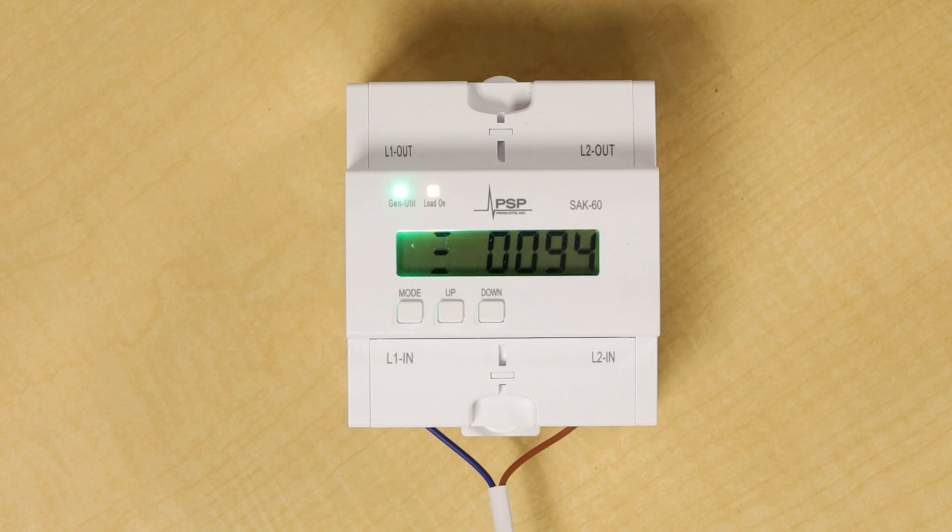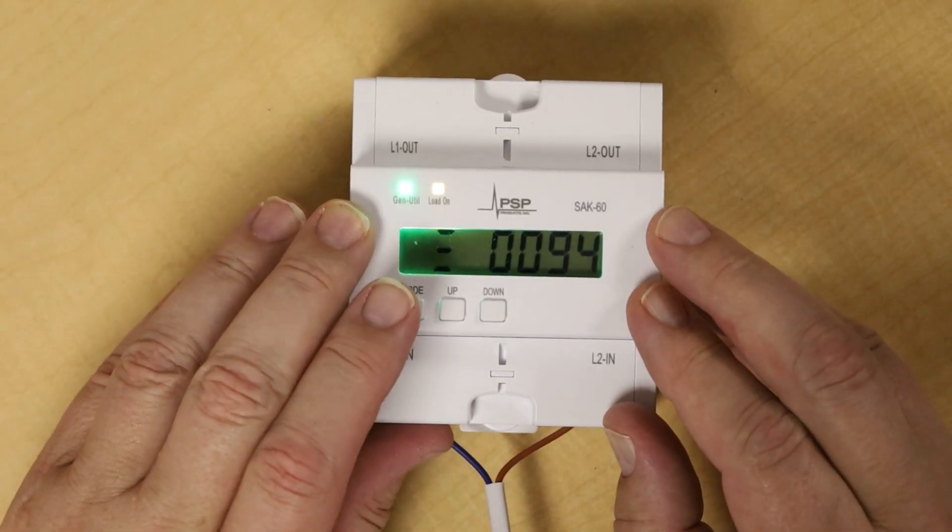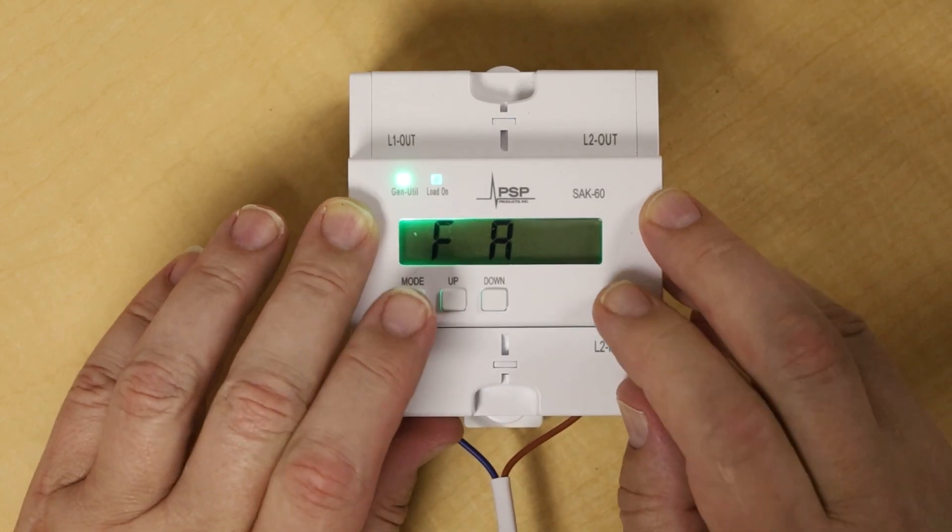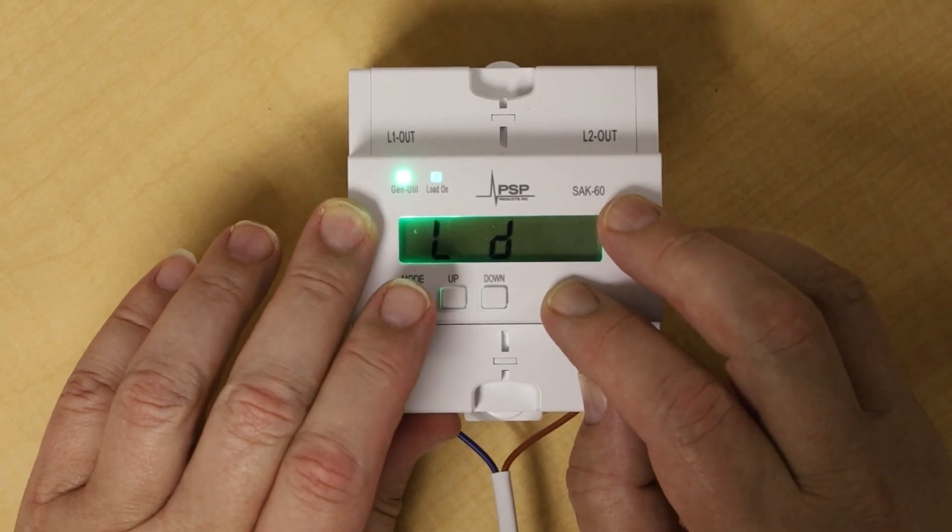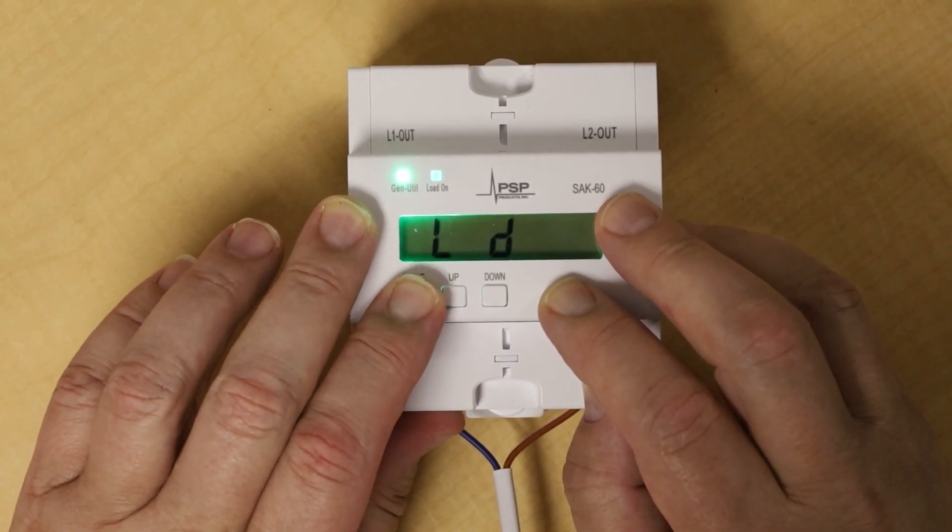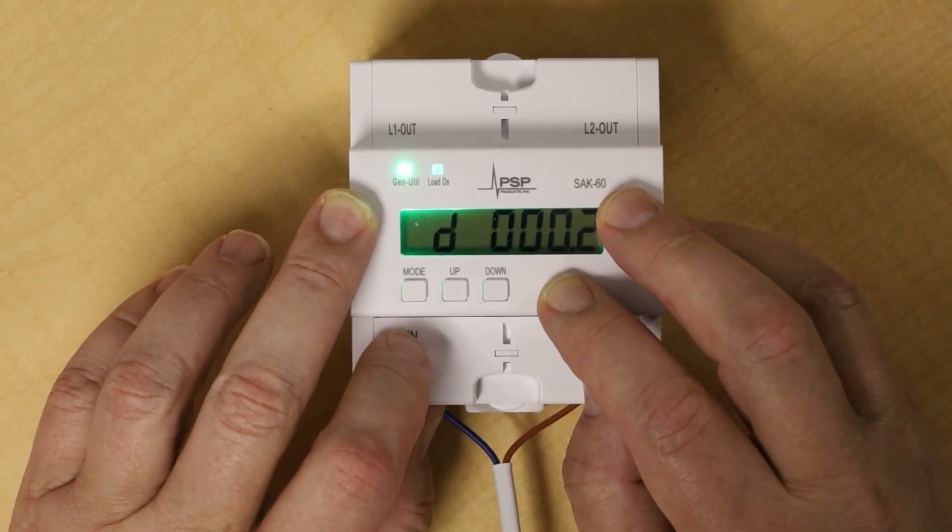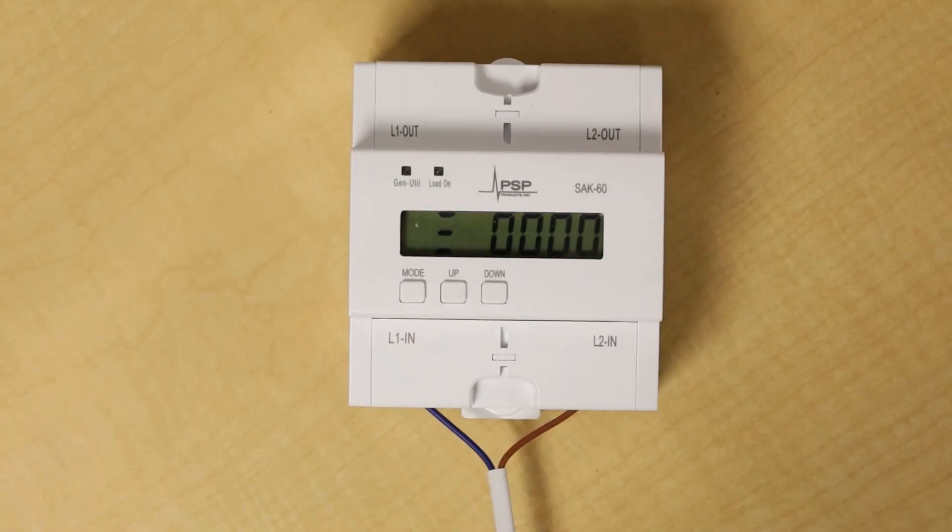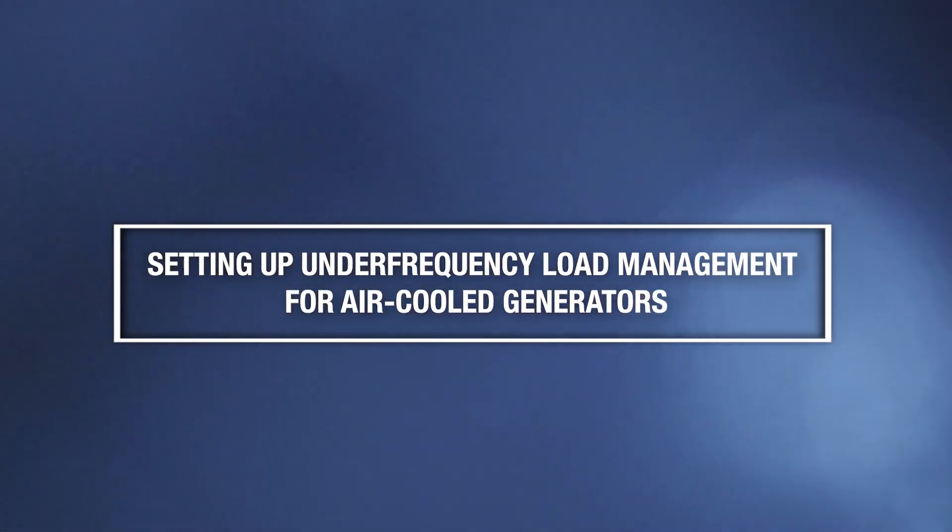To set up for generator lockout, first hold the mode button for about 3 seconds until FA appears. Press the mode button briefly to scroll to LD for load drop. Then hold the mode button again for 3 seconds to enter the programming mode. There's only one setting here, D000.2, which does not need adjustment. The SAK60 is now set for load drop, so that the load will be off any time you're on generator power.